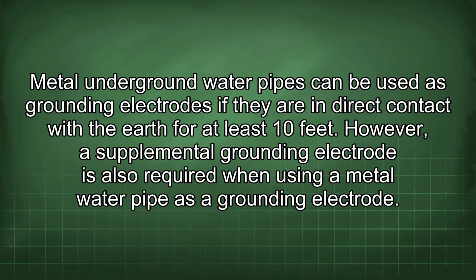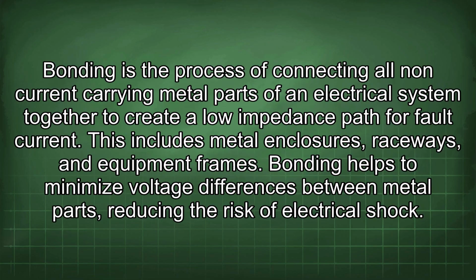Metal underground water pipes can be used as grounding electrodes if they are in direct contact with the earth for at least 10 feet. However, a supplemental grounding electrode is also required when using a metal water pipe as a grounding electrode. Bonding is the process of connecting all non-current carrying metal parts of an electrical system together to create a low impedance path for fault current. This includes metal enclosures, raceways, and equipment frames. Bonding helps to minimize voltage differences between metal parts, reducing the risk of electrical shock.